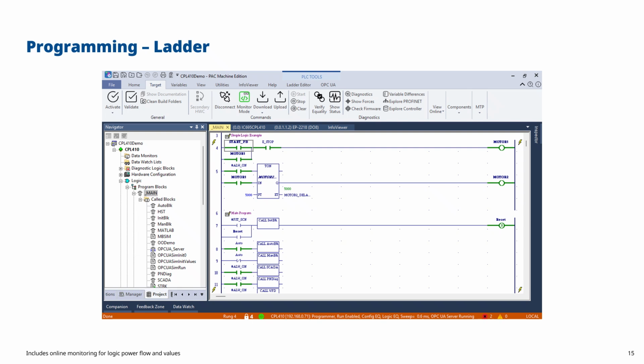Further down you can see we've got some more logic, and here we're calling some function blocks. I've got an initialization block which is called. Notice there's something that looks like a hash or gate, FST_SCN. The Americans might use the pound sign, but I'm British and our pound sign is different. The idea is that it's the first scan, a system bit that comes on in the first scan. So you don't need to program that bit, it's automatically in the system for you, ready for you to use. And we've got other contacts like normally open for always on, normally closed for always off, and so on. We've also got timer contacts and fault contacts. So there's a lot of contacts you can use there.